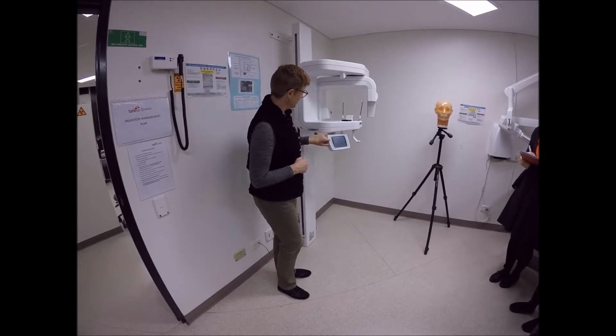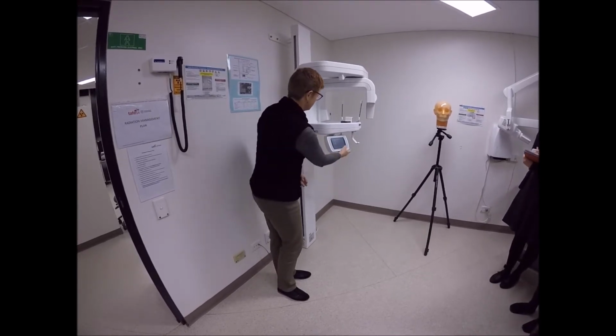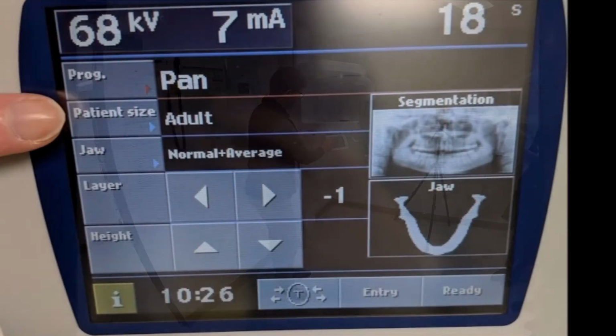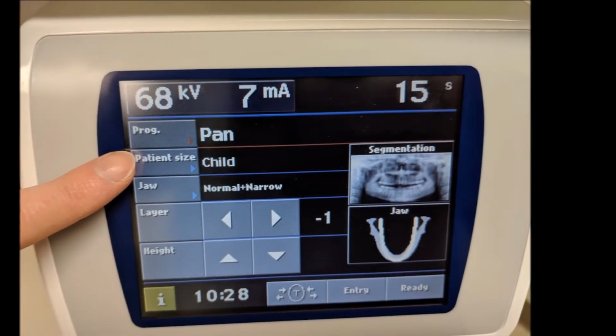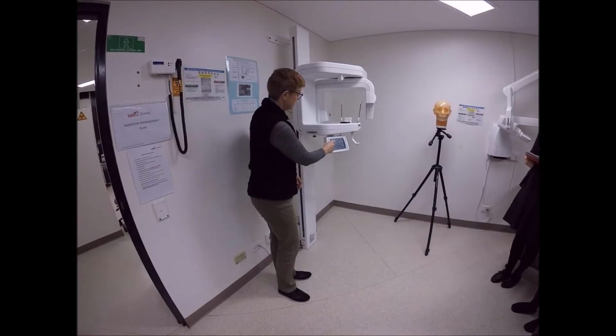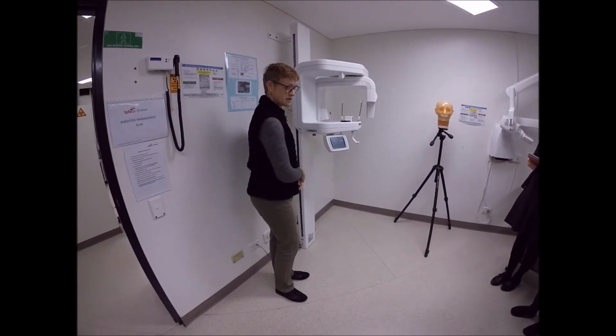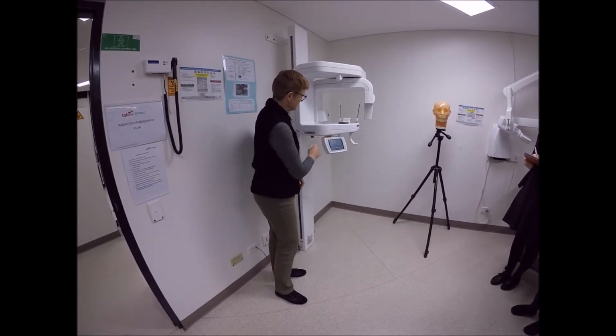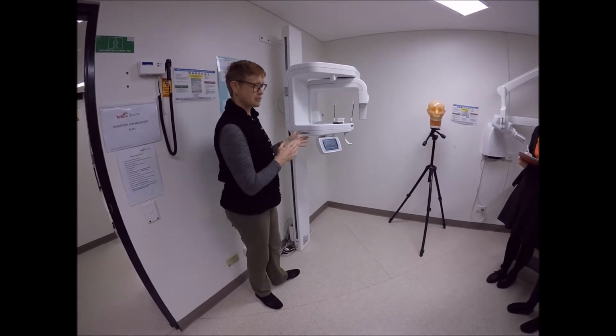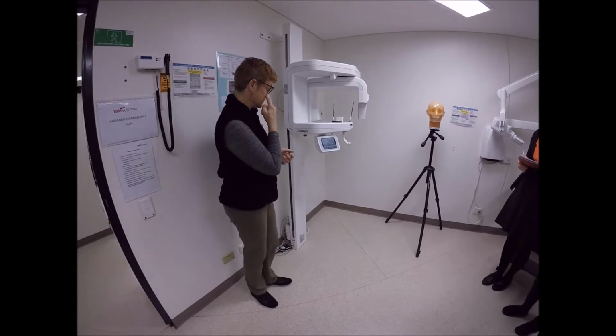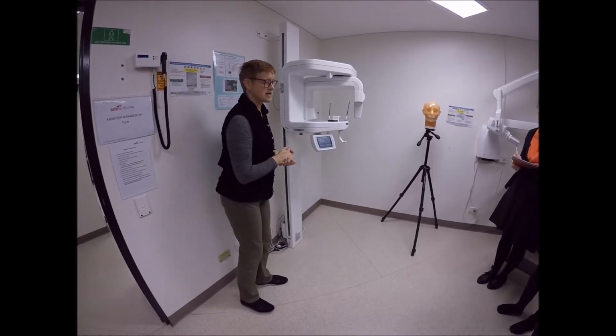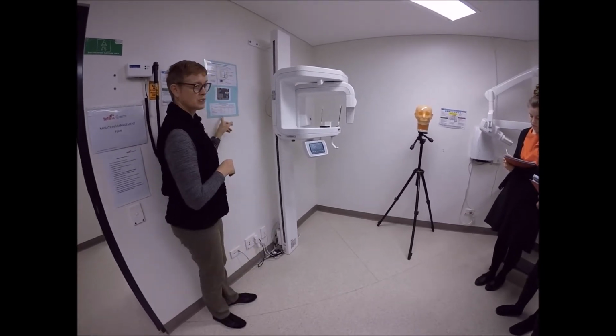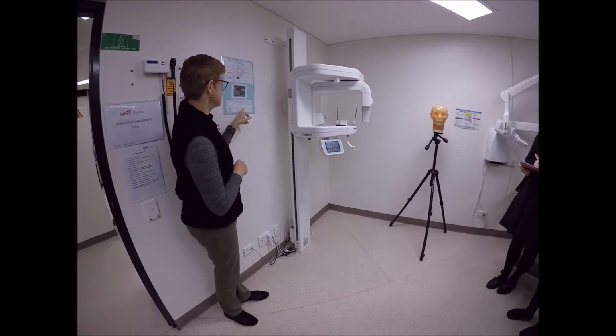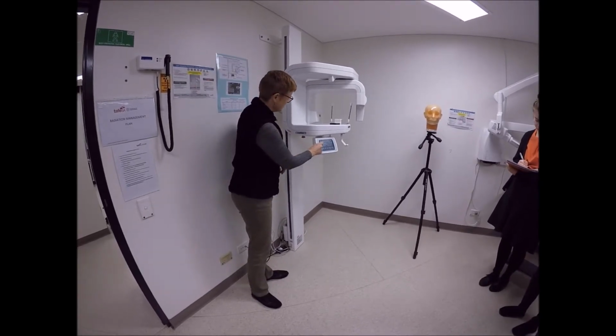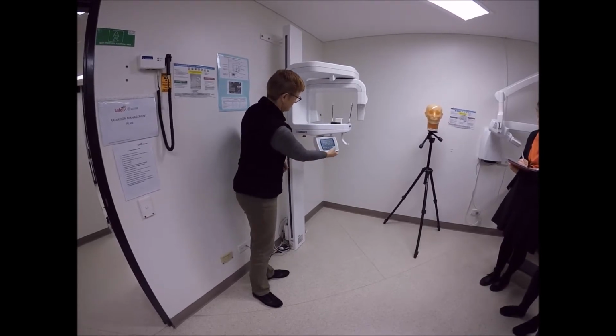We need to select adult versus child. This machine only gives us the option of adult or child. So Mr. Tester is an adult, we'll go for adult. We need to select the exposure parameters on this machine. There are no presets programmed into this software. So we're going to select exposures for him. Average adult, we're going to go with a standard or a normal exposure. We've got an exposure chart here on the wall if you forget. So average adult, we're going to use 68 kV and 7 milliamps. So we select 68 kV, 7, and press OK.